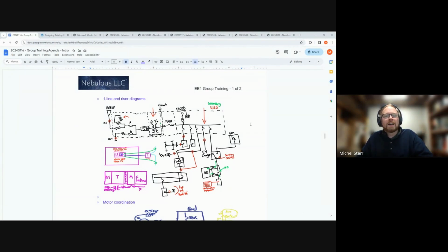So I don't know that exactly answered your question, Kayvon. I guess my suggestion is to rely on the one line, unless there is no one line. There are sometimes that I see that, and I hate when I see that. Personally, I'm sad because I'm like, oh no, I can't see how the project is connected. I don't even see the one line. It can be a small renovation project where it's just a panel board. Why even bother showing how the panel board's connected to everything else? And then yes, you would need to start with the panel schedule. But otherwise, if there's a one line and it has any degree of confidence, I would hold that as the higher degree of truth.